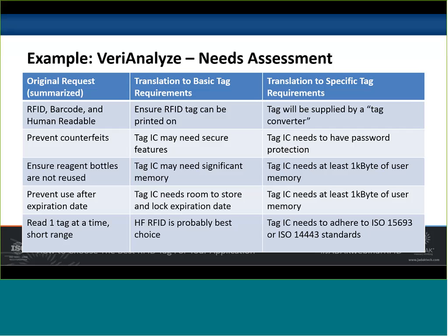That's possible as well, but in this case they just wanted simple password protection. To ensure the reagent bottles are not reused, we want the tag IC to have at least 1 kilobyte of user memory, based on what the engineers have told us. That 1 kilobyte would include enough room for the expiration date. And with HF RFID, we want to make sure our tag adheres to the main standards, either ISO 15693 or ISO 14443.